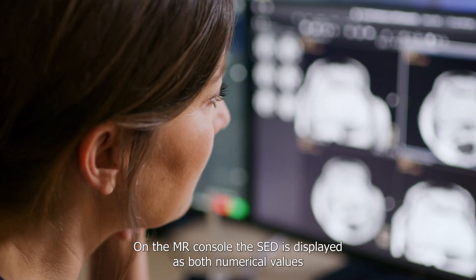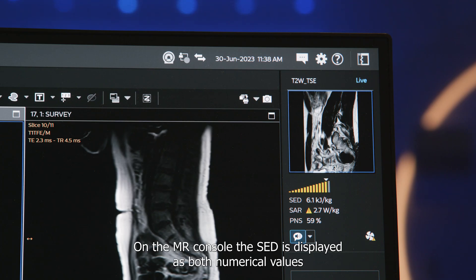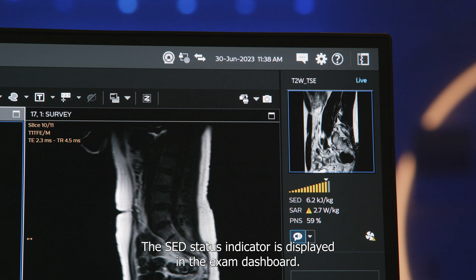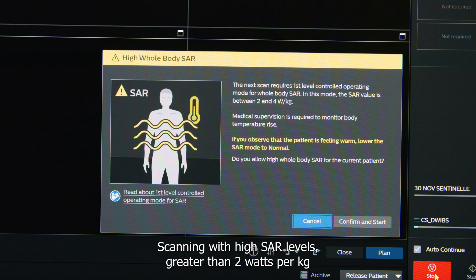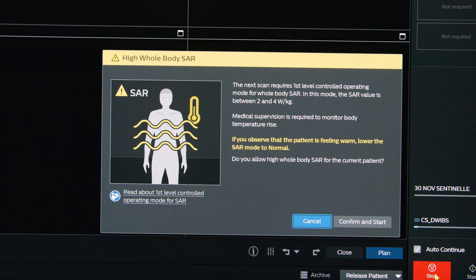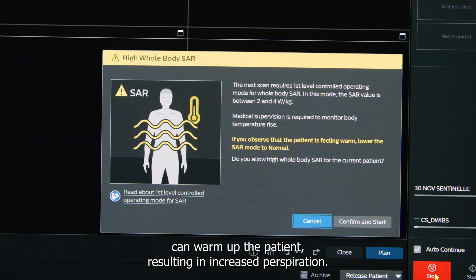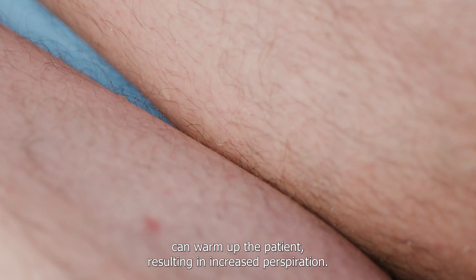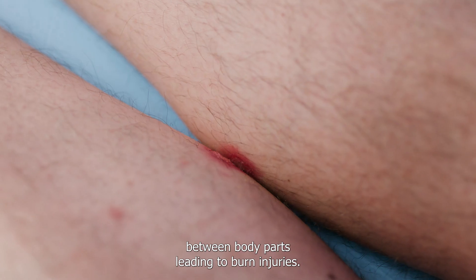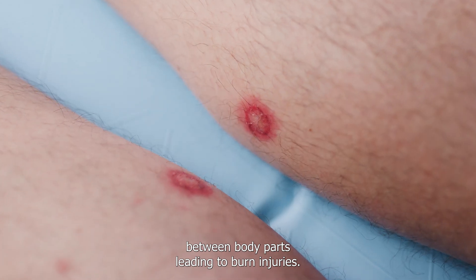On the MR console, the SED is displayed as both numerical values and as an overall SED status indicator, shown in the exam dashboard. Scanning with high SAR levels greater than 2 watts per kilogram, or scanning for a prolonged period, can warm up the patient, resulting in increased perspiration. Patient perspiration may result in unintended RF circuits between body parts, leading to burn injuries.